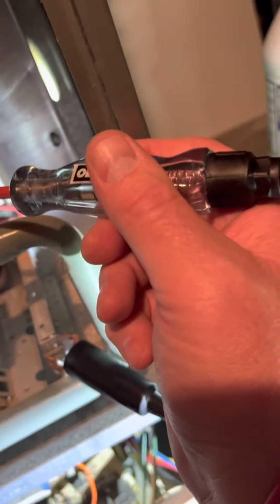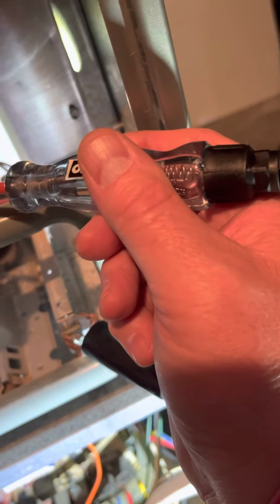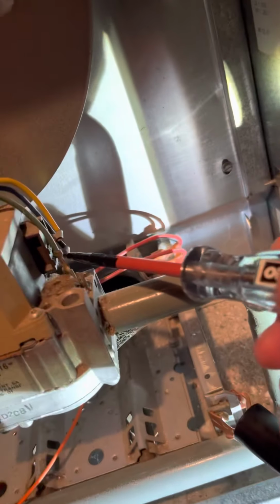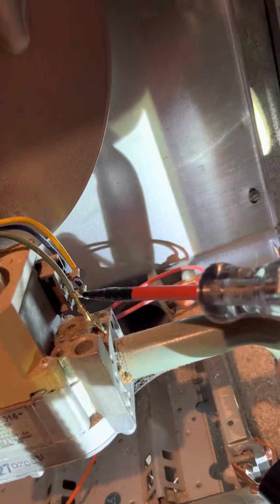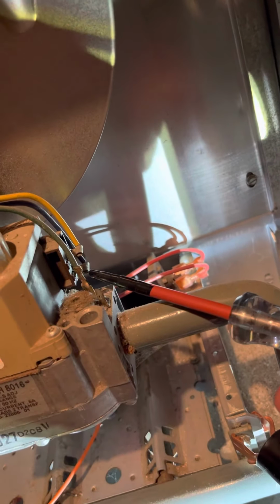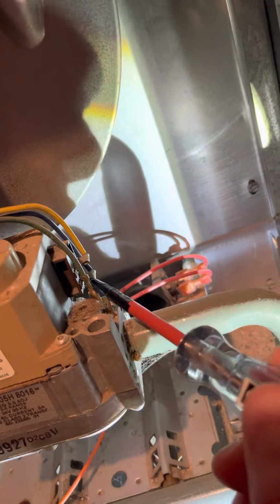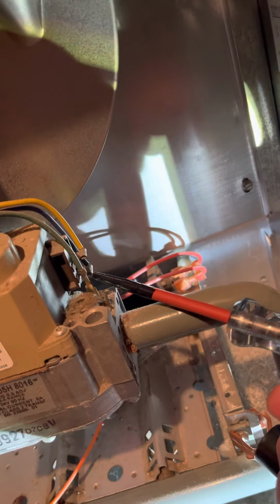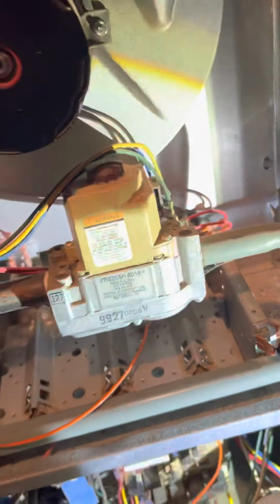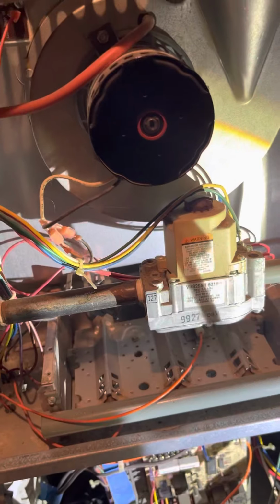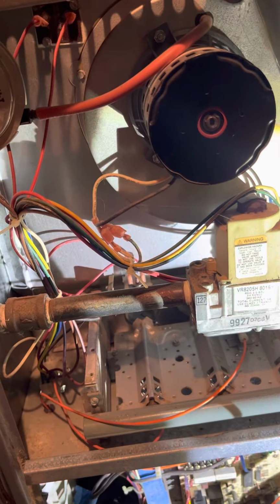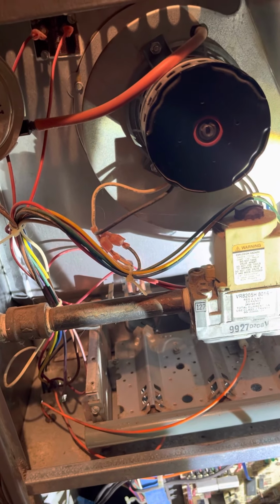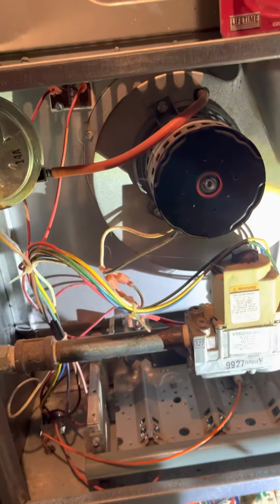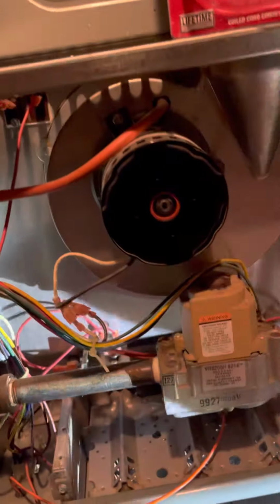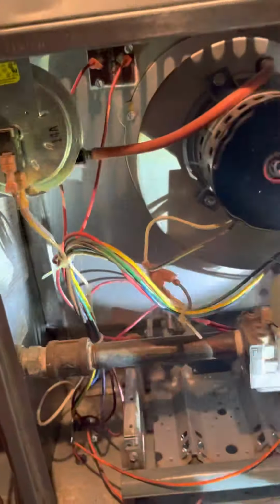And the reason you do that is because if we put this tester on a terminal or on a 24 volt wire, and then we accidentally touch the gas valve, or the gas line, or touch it to ground, it's going to be a direct short, and we're going to fry something, either the fuse or the board. So you have to be careful. So we're going to turn this on real quick.